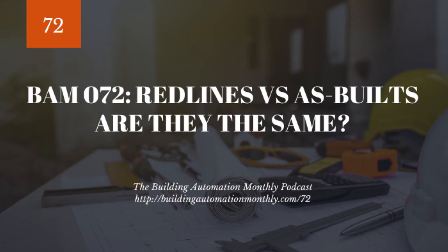Now, another area that you really want to be careful with redlines and as-builts is if you're using multiple technicians on a project. I've seen this time and time again where the mechanical contractor will redline, or they will make a change to their controls drawings. Maybe they make a change to the name of the boxes or the location of the boxes.